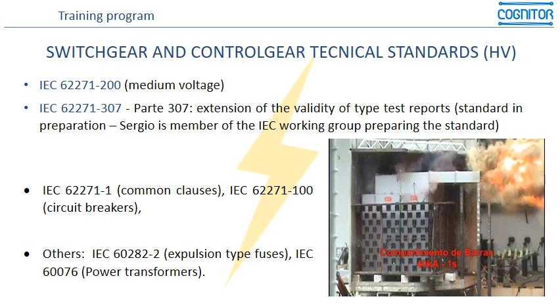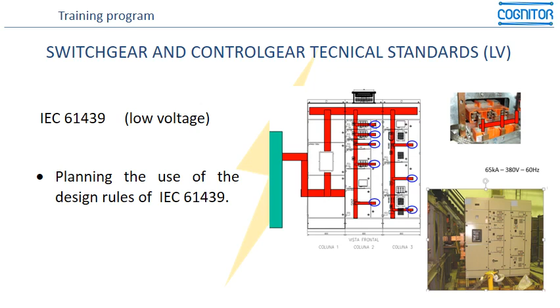For low voltage, we'll speak about IEC 61439 for low voltage switchgear, and the very important aspects opened up by the so-called design rules of IEC 61439. These design rules are new concepts implemented in 2011, which enable manufacturers to do much fewer tests than was necessary in the past. By using these design rules, you can avoid many tests, because you can base several conclusions on the results of one previously tested equipment, as we will explain.